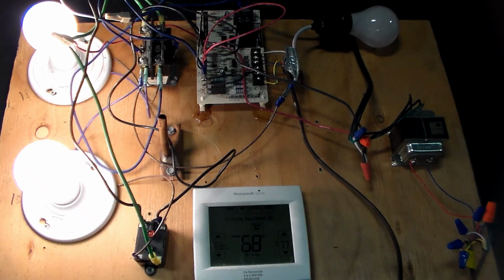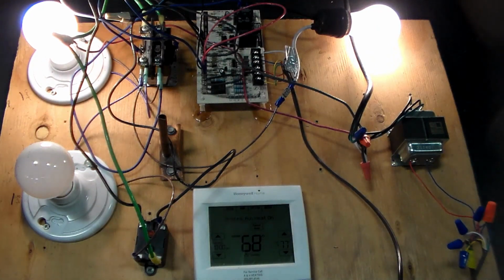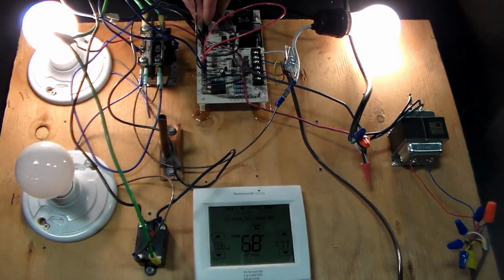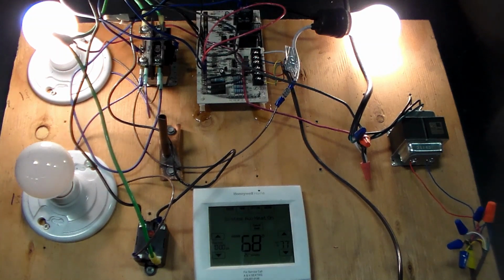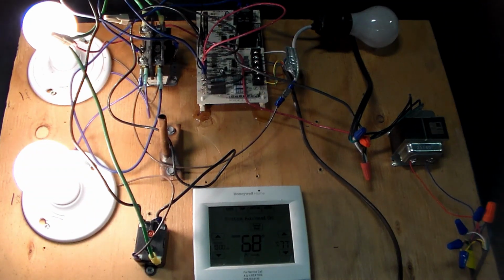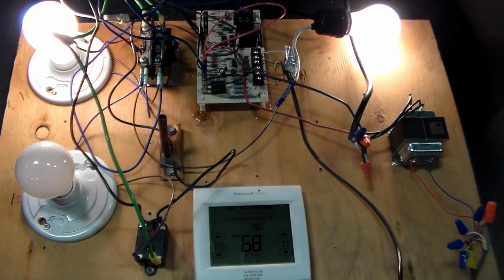The other thing I can look at is, if I jump it out to test mode, and I've had this happen before, that condenser fan doesn't go off because the switch of the relay is stuck shut. We know the condenser fan is supposed to go out during defrost, so that relay could be stuck shut. The other thing we could be having, but this one's more obvious because your condenser fan is not running to begin with, is the relay could be stuck open.